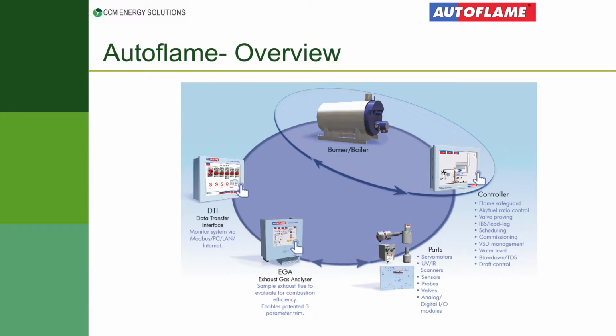With every Limpsfield burner, they come packaged with a combustion management system. This combustion management system, however, can be adapted to any existing boiler burner setup. Now, Autoflame were the pioneers of microprocessors for fuel air ratio control in the 80s when computers came into the marketplace. The owner of Autoflame said, let's use that to control combustion. Let's get rid of all the mechanical components, your cams, your linkages. Let's get rid of all of that and use direct drive servo motors. And that is how the whole concept came about. There are obviously other manufacturers out there, but this is where it all started.